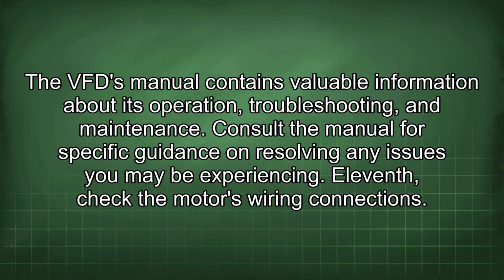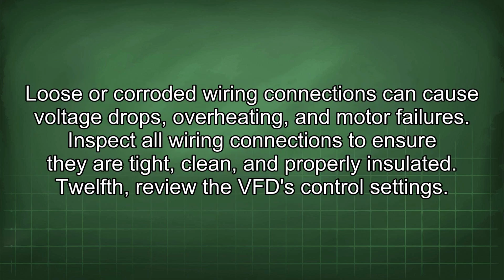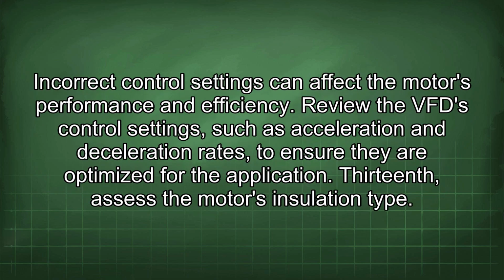11th, check the motor's wiring connections. Loose or corroded wiring connections can cause voltage drops, overheating, and motor failures. Inspect all wiring connections to ensure they are tight, clean, and properly insulated. 12th, review the VFD control settings. Incorrect control settings can affect the motor's performance and efficiency. Review the VFD control settings such as acceleration and deceleration rates to ensure they are optimized for the application.